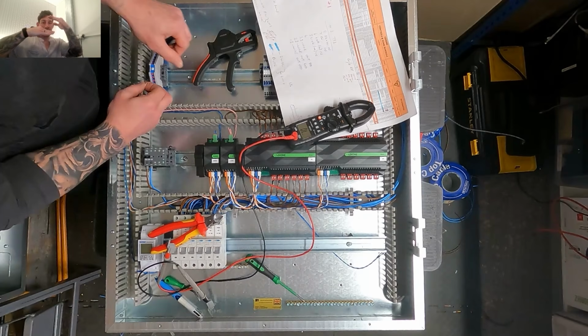They're not crossing, they're running parallel to each other. So I want to reduce as much as possible any potential for noise generated from that contactor switching the immersion on and off. I want to prevent it as much as possible being induced onto these cables because they're sensitive. That's why I've twisted those pairs, and you'll see later how I segregate the cables on the outbound side of the contactor from these cables.